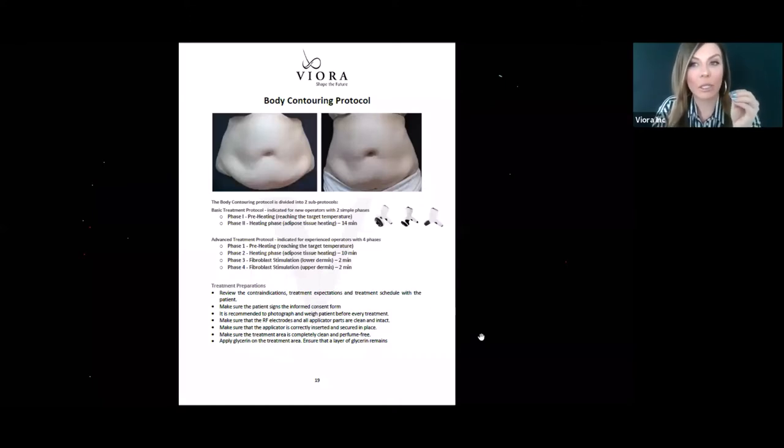We're always preheating the patient, and we're always preheating them in mode four, right? Because remember, mode four, all three depths are being preheated at the exact same time. So setting it to mode four, and then we need to select our RF energy level and our vacuum level. So remember, we talked about the vacuum. We have a level between vacuum one and four we can choose. And then we have the exact same thing with the RF. We have an option between one and four.